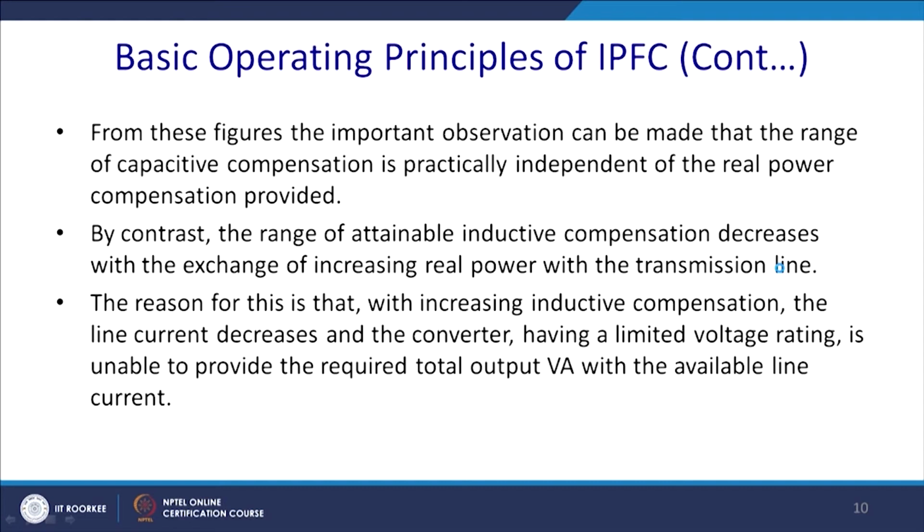By contrast, the range of the attainable inductive compensation decreases with the increase of the real power exchange with the compensated line. So, this is one of the disadvantages. It can compensate capacitive VAR quite well, but since the line current decreases, since you are exchanging the real power, the inductive capability will be reduced, but generally loads are inductive. So, this is why the IPFC is not put in a very dominant position among our FACTS devices.